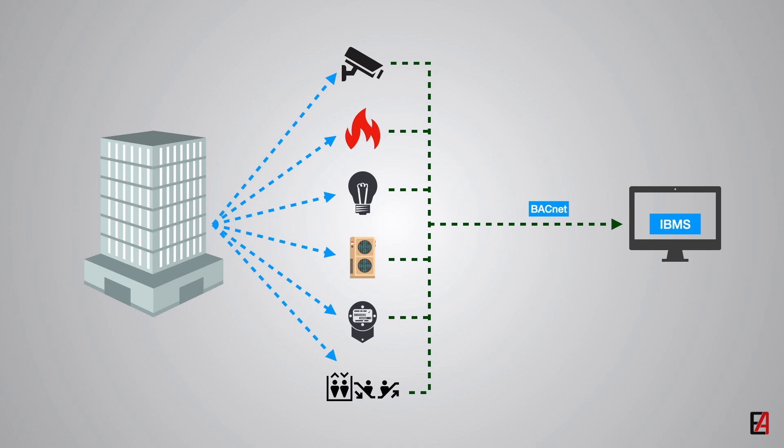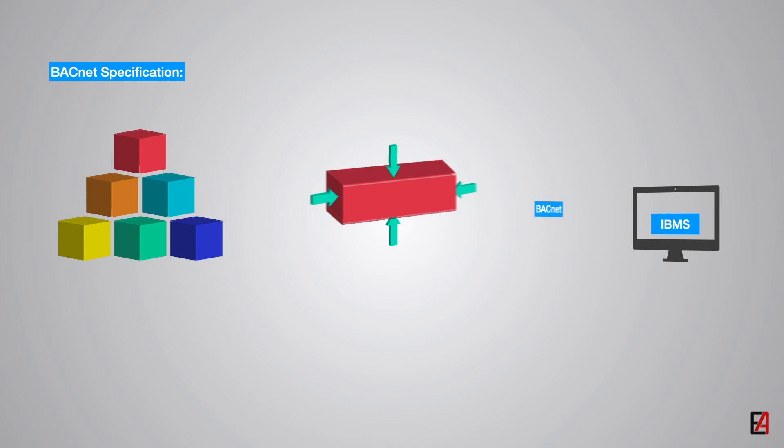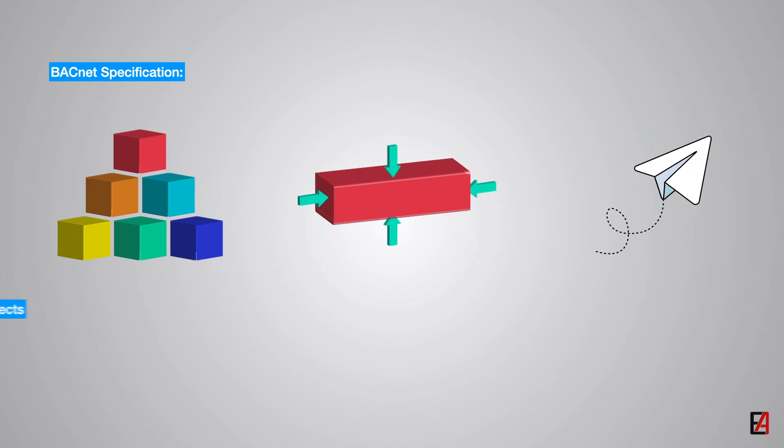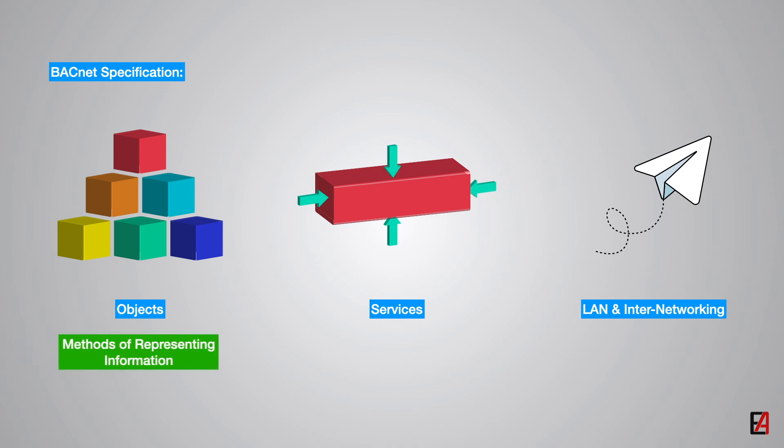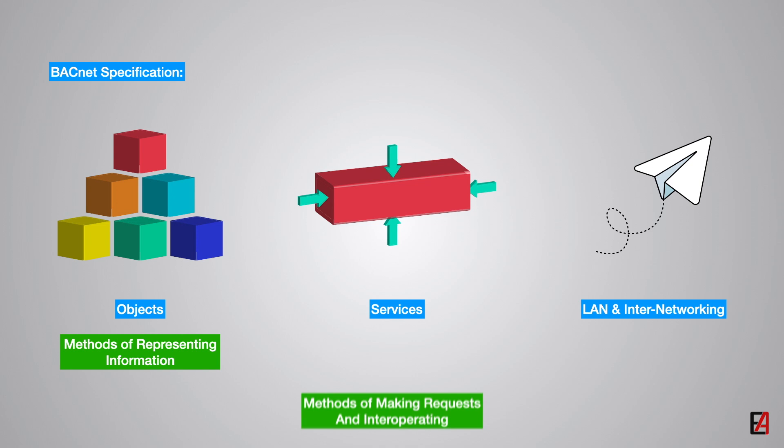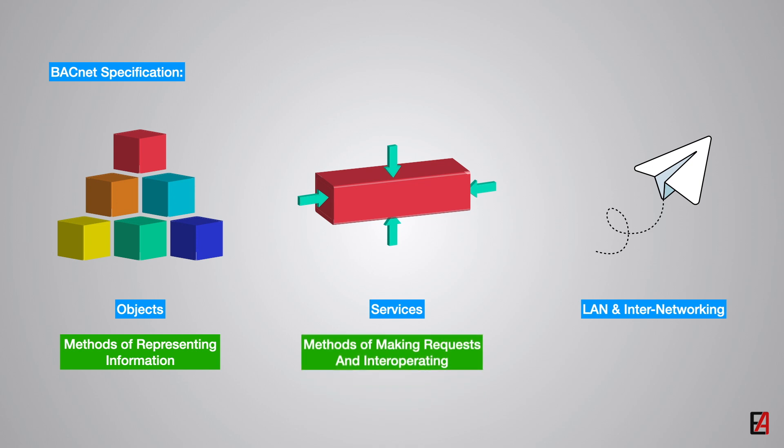The BACnet specification has three major parts: objects, services, LAN and internetworking. The first part describes a standard way of representing the building automation equipment. The second part defines messages that can be sent across a network to monitor and control the building automation equipment. And that part defines a set of acceptable LAN communications with a selection of various network transport technologies.